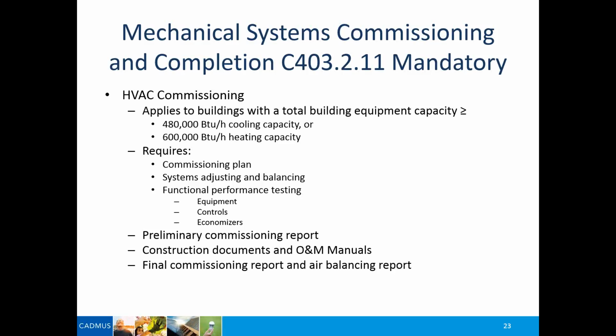Some of these will not apply to you. Obviously, the economizers, you are exempt from the economizer requirement in the code. But some of the other requirements for controls, obviously you need to make sure that they operate correctly, and there's some criteria in the code. And then once you've done this, you submit a preliminary commissioning report, and that preliminary commissioning report will essentially say, we did the testing, here's our findings, here's what we need to fix, here's what we need to make sure that it actually works. The preliminary commissioning report, the building department can require you to submit that to them to make sure you've done it.